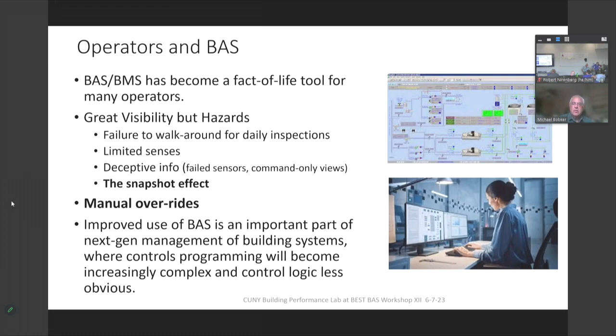Even worse is what I'd call command-only views, where we don't have a full feedback loop. The installation was done, to put it bluntly, on the cheap, and the actual status of the commanded component was not wired back to the BAS. So what you see is the command, and if you're not sensitive to that, you think something's been commanded, but it hasn't happened—a belt broke, a drive motor failed, a linkage came loose, whatever. So the status of the equipment is not what you're seeing in the command-only view.